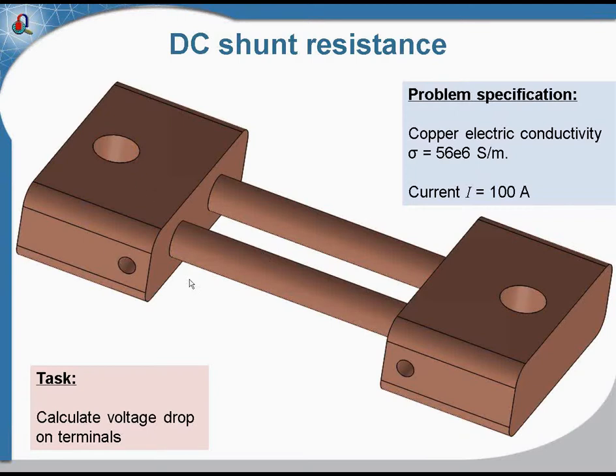The voltage drop across the shunt terminals is proportional to the current flowing through the shunt. Since the resistance of the shunt is known, the voltmeter connected to these terminals can be scaled to directly display the current value. The large holes are used to connect the bus bar, and the small holes are used to connect the voltmeter.